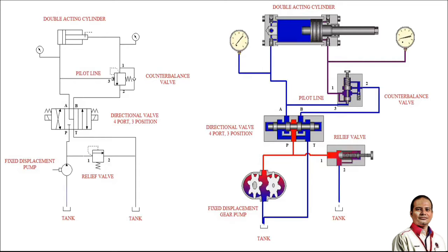Okay, so the next frame is actually a spool shift to the other direction. So this is to the right. So this correlates with this spool position, P crossing over to B, A crossing over to T. P is crossed over to B. See, this spool came off its land and opened up that little bit of a flow path right there. There will be a decent pressure drop across the spool depending on the design. There's a lot of factors that affect that.